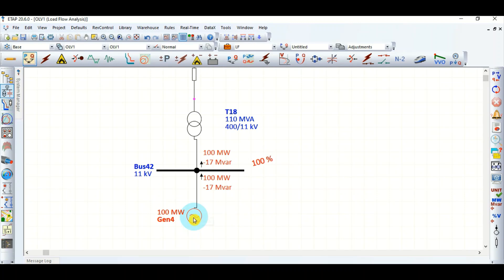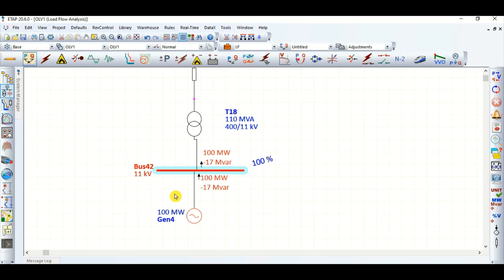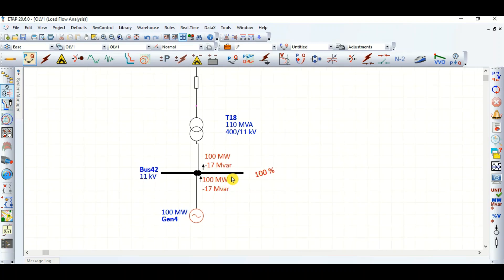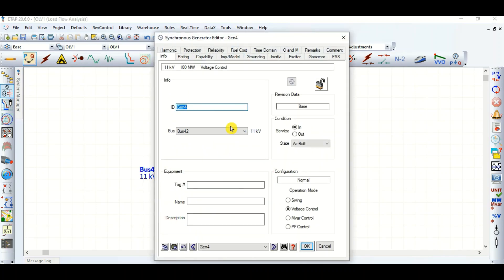To avoid damage to the generator, it is absorbing reactive power and keeping the generator bus at 100% voltage. It is maintaining 100% voltage because we have set the generator in voltage control mode.